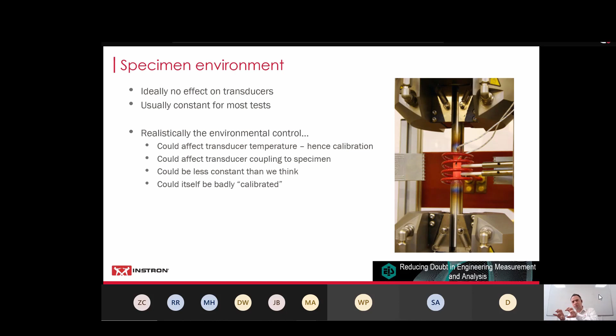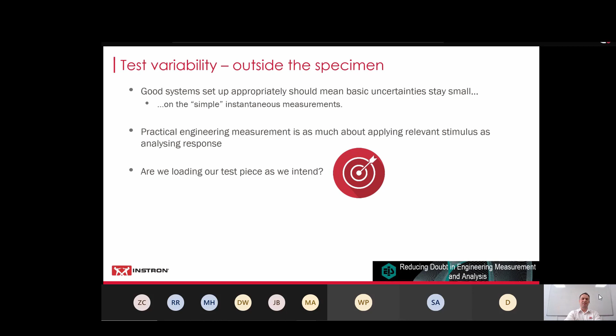So we're starting to talk about test variability, and let's think about test variability outside the specimen or outside the material itself. As I've said, if we've got things set up appropriately and we've got a good system, those basic uncertainties on things like force and strain, we can get them small. However, when we talk about practical engineering measurement and simulating loading, which is effectively what fatigue testing is, it's as much about applying the relevant stimulus as about analyzing or measuring the response. So we need to ask the question: are we actually loading our test piece as we intend? Let's first talk about the literal interpretation of that. The control fidelity: are we hitting the targets?